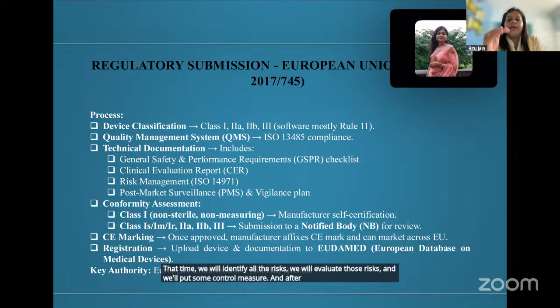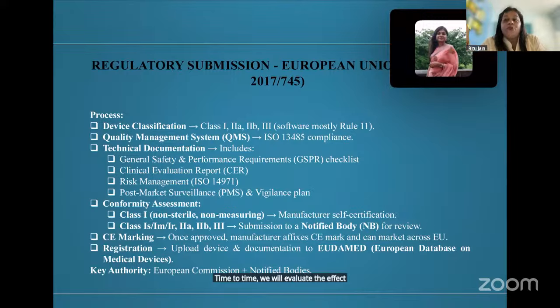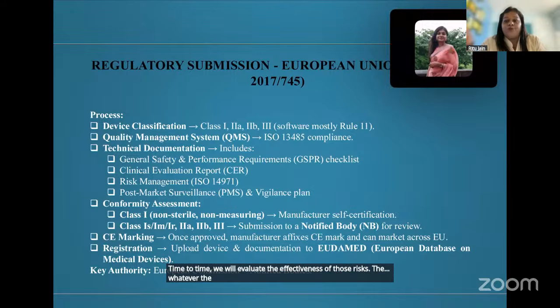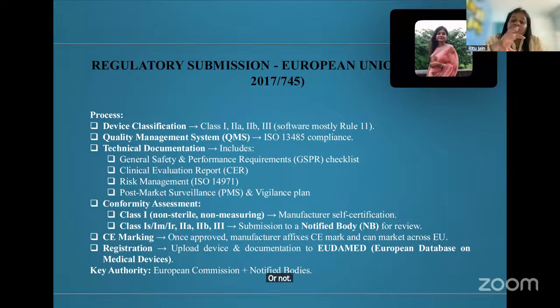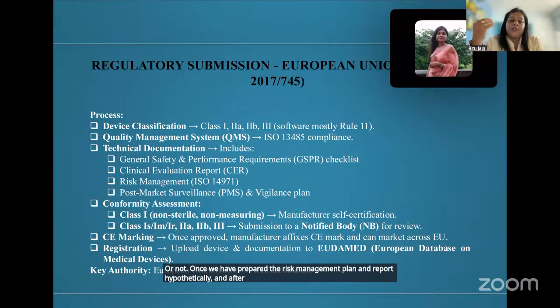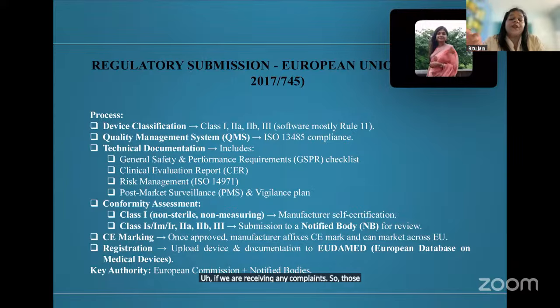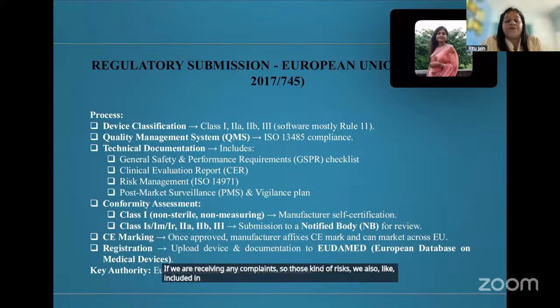And after putting the control measures in place, from time to time we will evaluate the effectiveness of those controls, whether the control measures we have taken are actually working or not. Once we have prepared the risk management plan and report, and after producing the product, in post production we also consider the risks in our risk management file. If we receive any complaints, those kinds of risks are also included in our risk management file, and from time to time, or on a yearly basis, we have to update the risk management file.